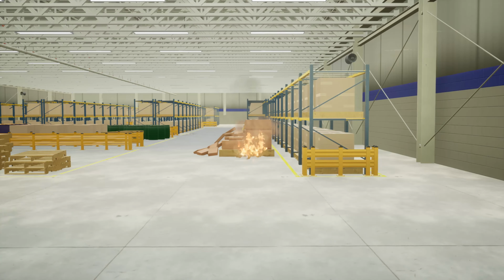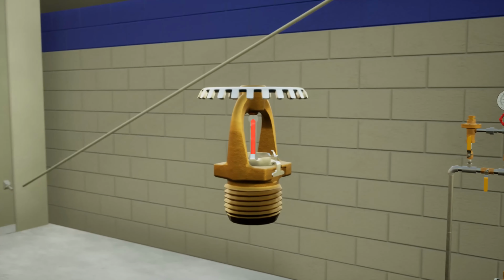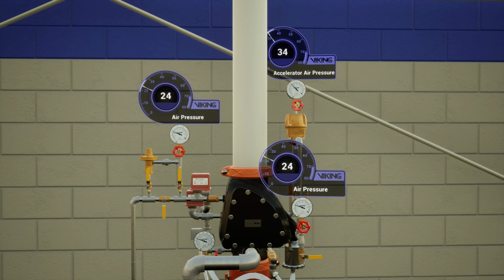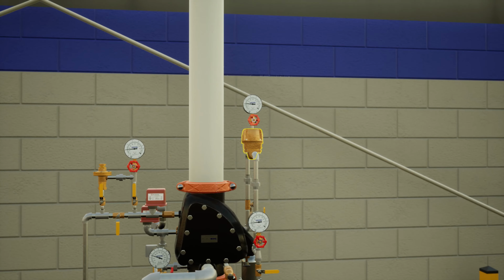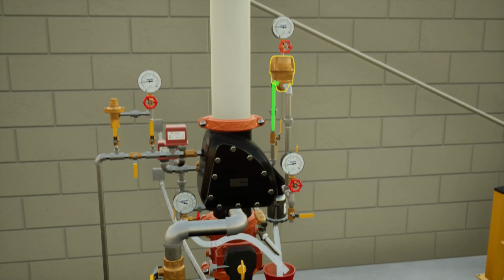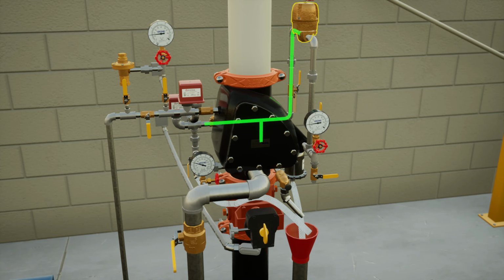In a scenario where a fire has started in the warehouse and begins to grow, sprinklers will operate. Air escapes through the operated sprinklers, causing the air pressure within the outlet of the valve, the trim, and pipes to drop. With the equipped accelerator, the slight but sudden drop in air pressure from the sprinkler operation causes the accelerator to activate and air is redirected to the intermediate chamber of the VXR valve, adding additional pressure under the clapper.